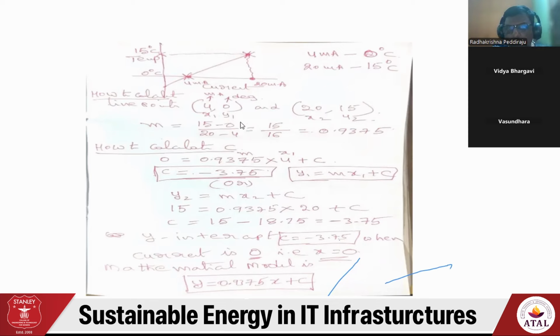So my Y value is 15 minus 0. And the current values which the sensor gives is 20 to 4. So I've taken X range as 20 and Y range as 15 minus 0. Now I got the slope of my line, which gives me the M parameter. Instead of decimals, I wrote it so you can understand, 15 by 16.